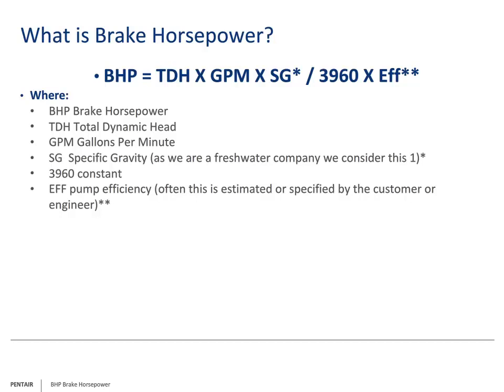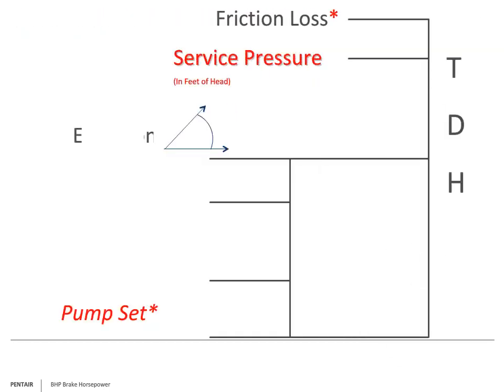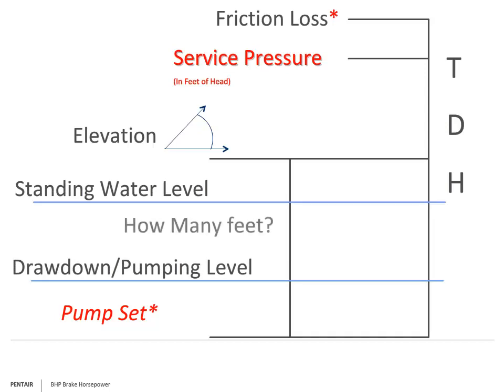Now we know what the formula is, let's put it to practical use. One question often asked is: what is total dynamic head? Looking at this simple diagram, it is friction losses throughout the system, pressure converted into feet of head, elevation, standing water level, and more importantly the drawdown. Adding all these factors will give us total dynamic head.